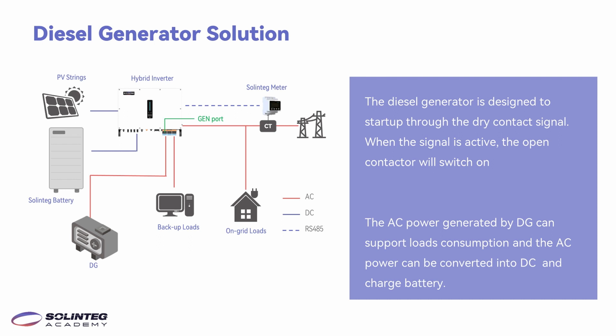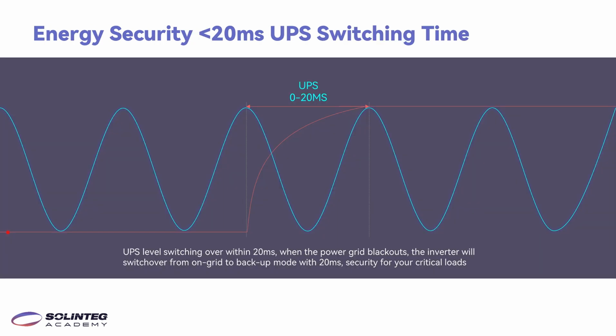When the signal is inactive, the open contactor will switch off, so the generator will be turned off. The AC power generated by the generator will support the load consumption and charge the battery. In this part, we want to introduce how we get the less than 20 milliseconds switch time.